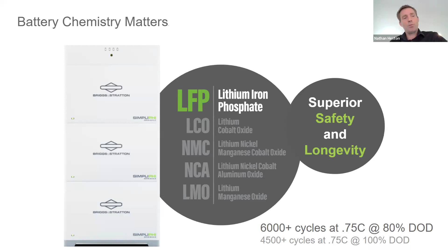Even though we're looking at fast discharge cycles, we're still looking at over 6,000 cycles. The reason there's a plus here is because if we discharge it very rapidly at 0.75C, meaning we discharge that battery in 1 hour and 20 minutes, we're expecting 6,000 cycles. Most customers aren't going to discharge their battery that quickly every time - they might do it occasionally. So we expect they'll probably get a lot more cycles than we get in the engineering lab, where we're running it really fast.